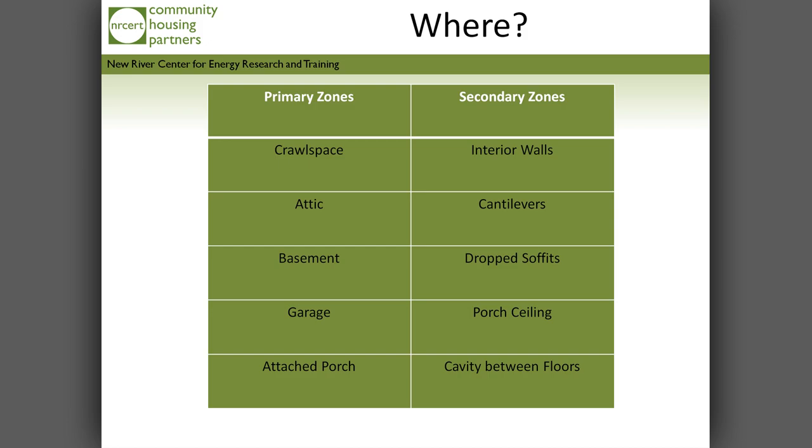Is it connected to the house? Do we want it connected to the house, typically? No, not really. The attic, do we want it connected to the house? No. In specific cases, like closed crawl spaces, that's different. In that case, you will be bringing the crawl space into maybe conditioned space or closer to conditioned space, because you've moved the thermal and pressure boundary from the floor location all the way to the walls. That's a very specific application, and in that case, it's okay.